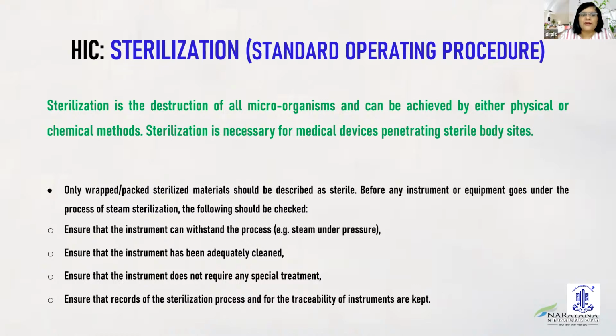We have to remember that only the wrapped and packed sterilized material should be described as sterile. Ensure that the instrument can withstand the process, that is steam under pressure, for steam sterilization. Ensure that the instrument has been adequately cleaned. Ensure that the instrument does not require any special treatment, and ensure that the records of the sterilization process and for the traceability of the instruments are kept.